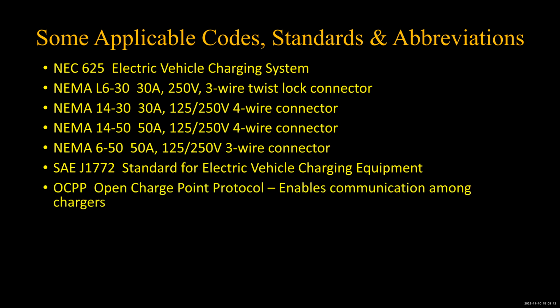This OCPP is interesting, Open Charge Point Protocol, and that enables communication among different chargers, so you could have like 10 chargers all working together, except you may have a limited demand. You may want to do demand limiting. So these chargers can talk to each other and share, and say, okay, either we all back off and do 5,000 watts instead of 9,000 watts, or half of us do 9,600 watts while the rest of us shut down.